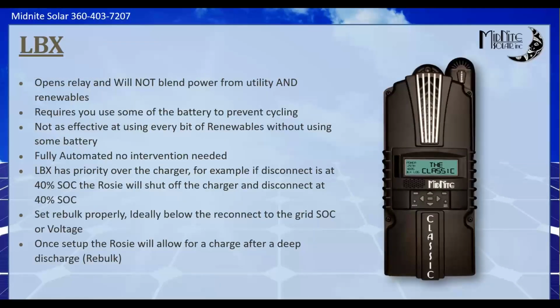So LBX mode. LBX is probably one of my more favorite modes because it's very defined. There's no gray. It is black and white. It's either using the grid or it's not using the grid. The only downside I have to LBX mode really is that it doesn't blend power. May not be a problem for most cases. Like I said, if you're running it that way, no real issue. It physically opens the relay. So when we hit our trip point, we're going to open the relay and ignore the utility grid until we reach our next trip point, which is a reconnect, and then we're going to go back and connect to the utility grid. So because of that, you have more flexibility on your charger too.